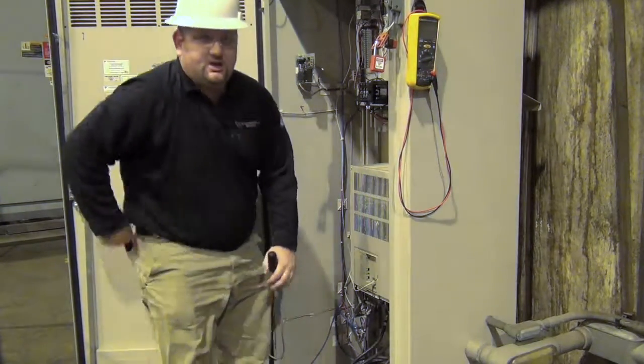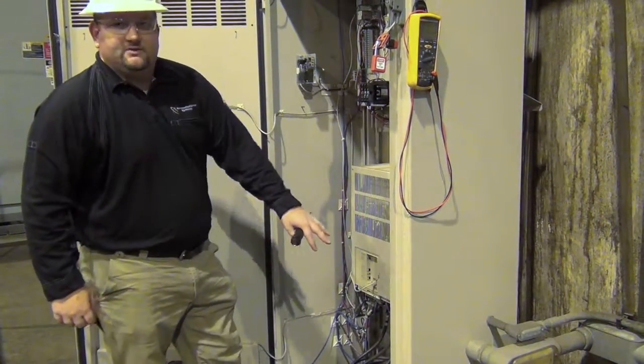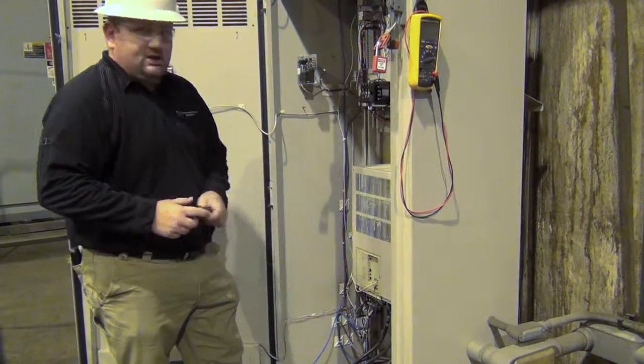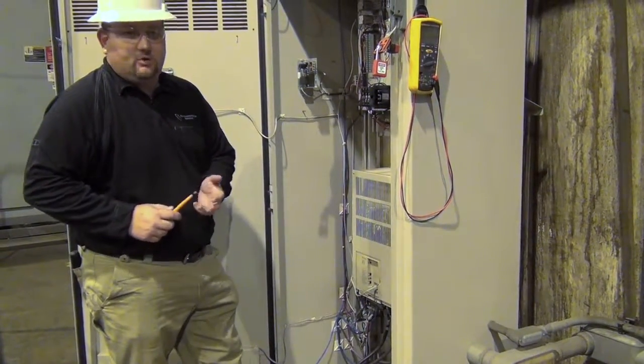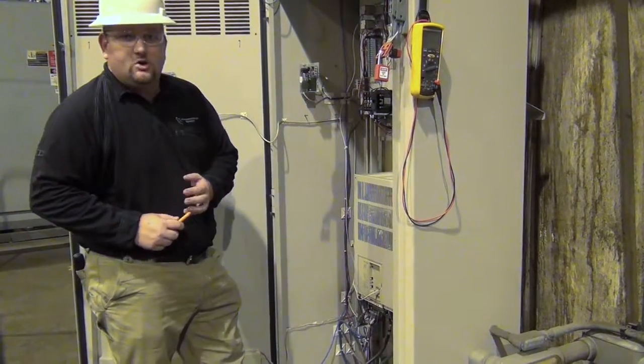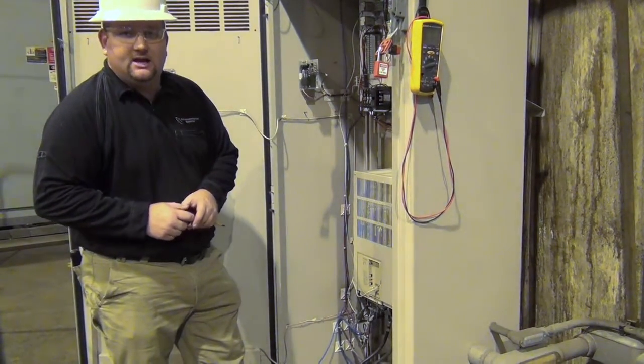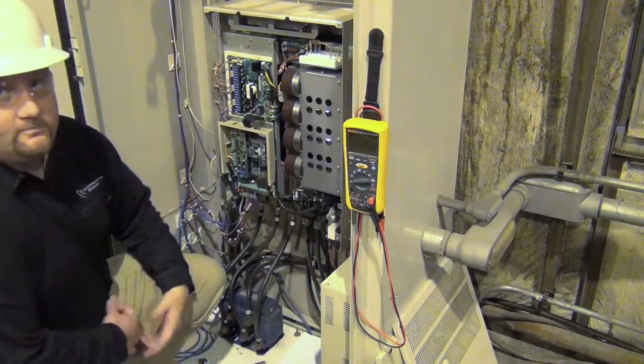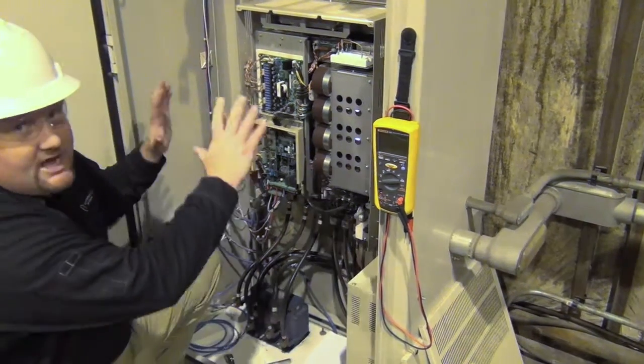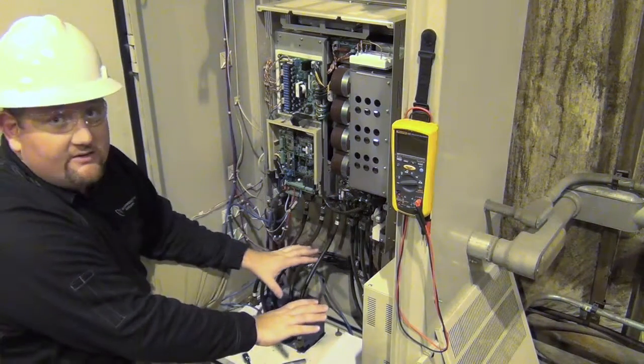So now what we're going to do is go ahead and take all the front covers off of the drive so that we can give a visual inspection on the capacitors, the control circuit boards, as well as check the torque on the main incoming and outgoing line connections. So now we have the drive all opened up, we've taken all the covers off of it.